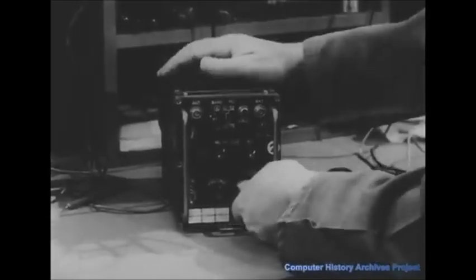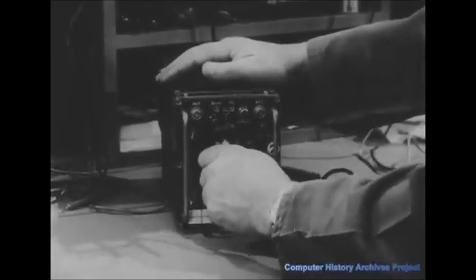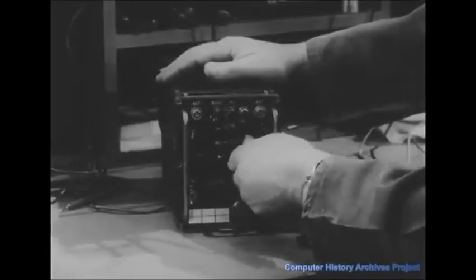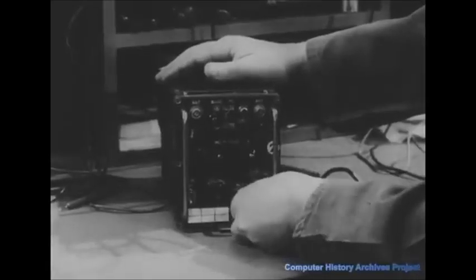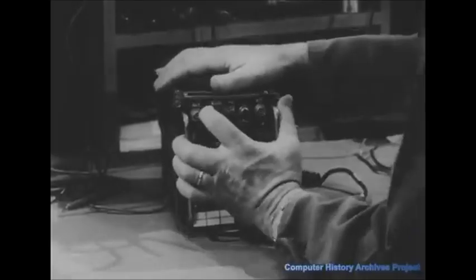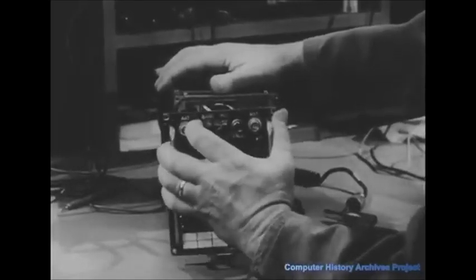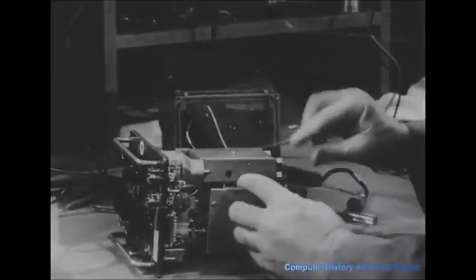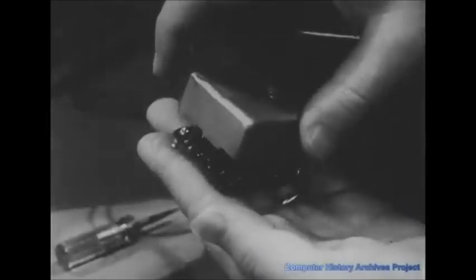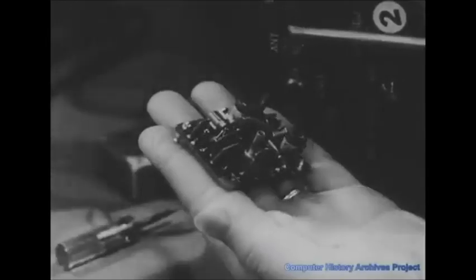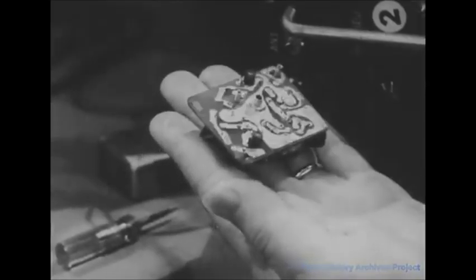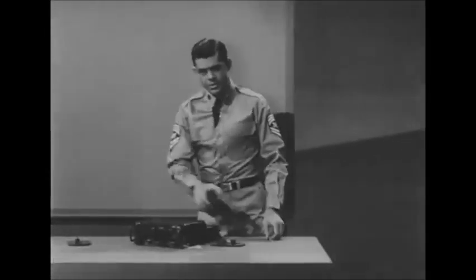Whether the equipment uses transistors, tubes, or both, the visual check should definitely include fuses and fuse holders, the cabling and cabling connections, loose, missing, or scraping front panel controls. Inspect interior for broken wire and wire connections. Once the trouble has been localized to a particular module, it should be carefully inspected. The inspection of a module should include the following items.